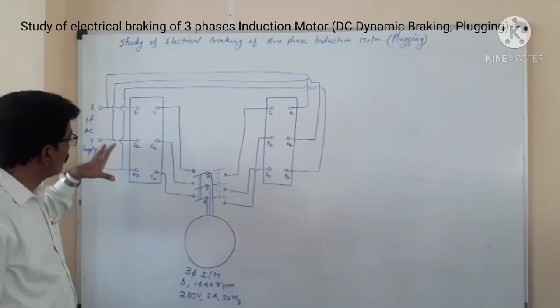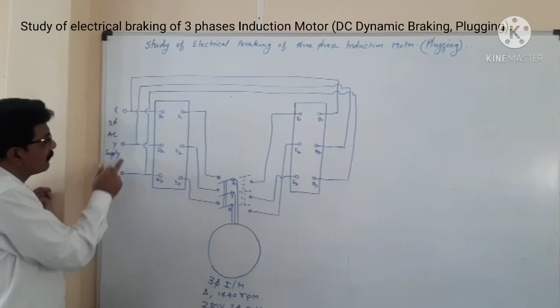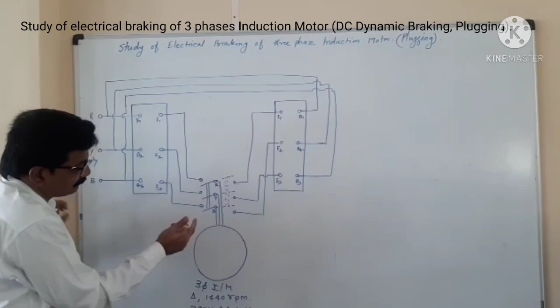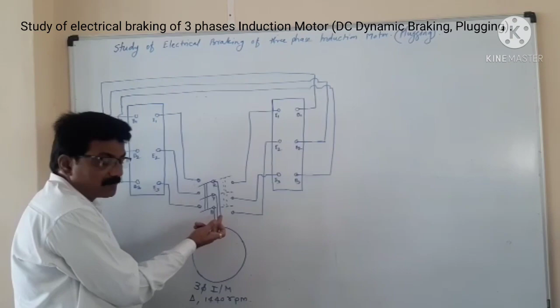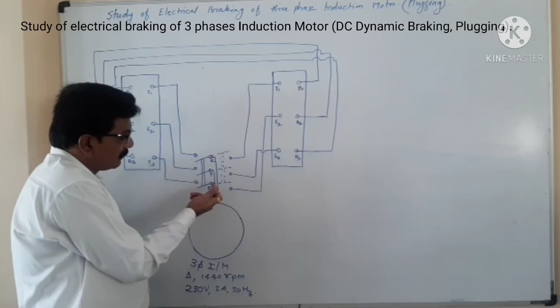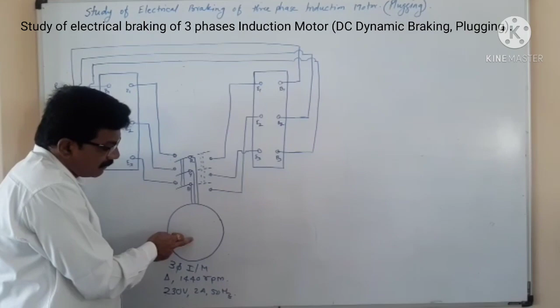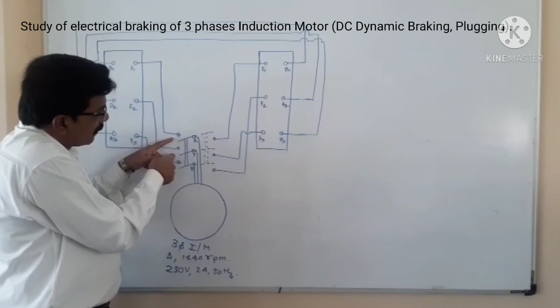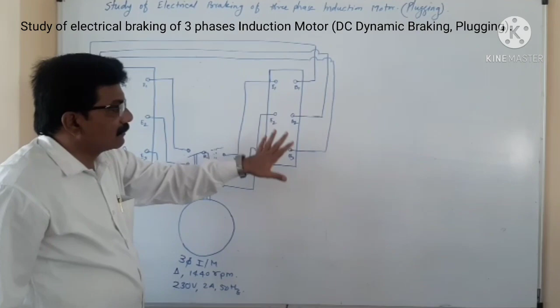Here, two three-phase auto transformers are connected from the three-phase supply, with phase sequence RYB. This RYB is connected to one switch, a triple pole double throw switch, whose center poles are connected to the induction motor, one set of poles connected to one auto transformer and the other set to the second auto transformer.